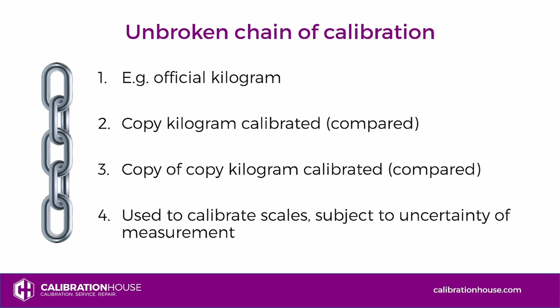So we'll take the kilogram as an example. Somewhere in the world, there is an official kilogram. Now, the definition of the kilogram actually changed recently. The original kilogram had lost approximately an eyelash worth of weight or mass over time. So it has changed to a more accurate way to measure a kilogram. So Google that if you'd like to learn more. So you take a copy of the official kilogram and you compare or calibrate it against the official kilogram. There's then a copy of the copy, which is compared or calibrated against the first copy. That is known as your local standard. You take your local standard, your kilogram, and you can use this to calibrate scales subject to the uncertainty of measurement.